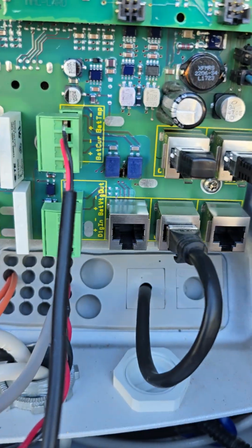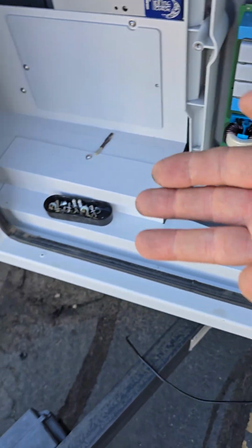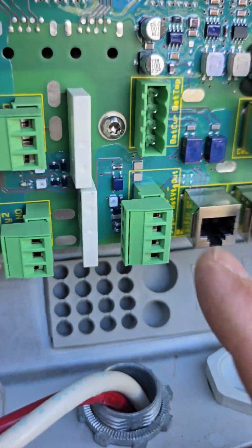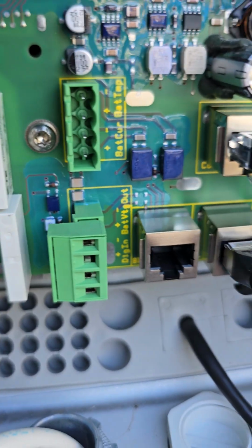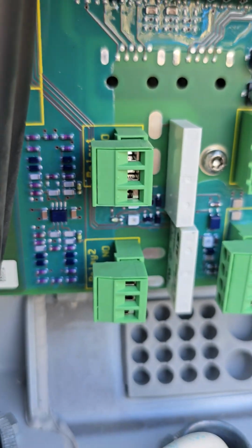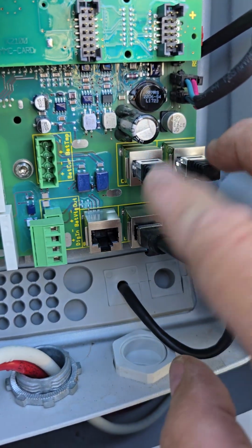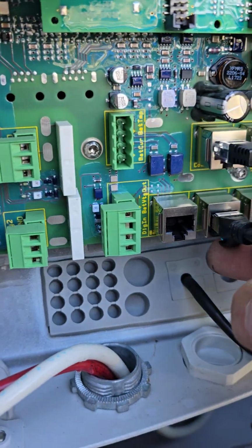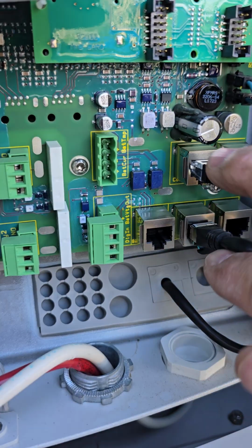I have it down here, but there's the battery current sensor and the battery temp sensor. You just have to run little wires underneath the trays here over to the slave and then hook them onto here, into the battery current sensor, the battery temp sensor, and of course relay 1 for the generator. That's about it. And then this guy becomes your master. Well, and then you also want to reverse these little communication ports. So this guy would come up from the bottom, up top, and then the terminator down. You just kind of reverse the role of the network.